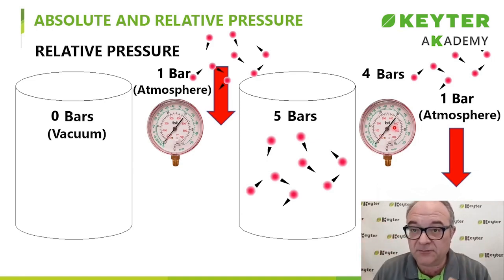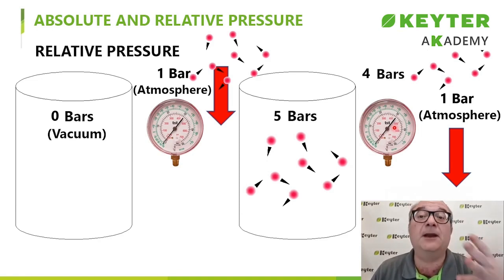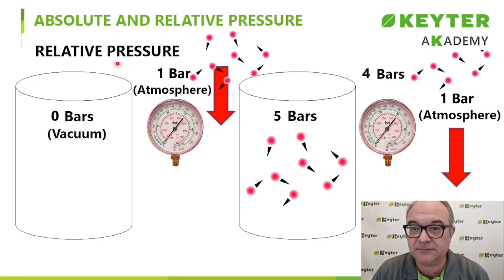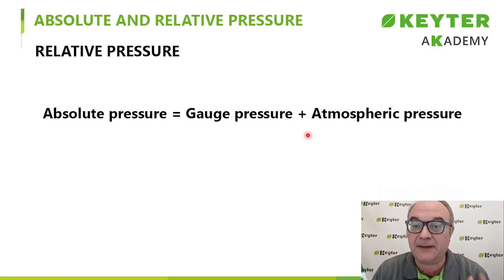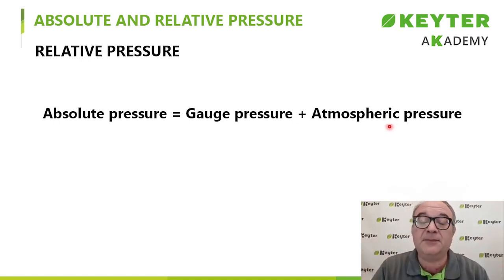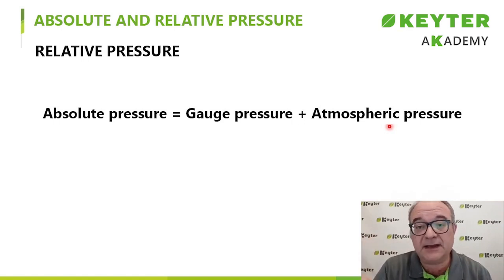This is very important because when measuring, we need to know that we are measuring relative pressures. By adding 1, which represents atmospheric pressure, we can calculate the absolute pressure, which is the actual pressure inside the tank. Thus, absolute pressure is gauge pressure plus atmospheric pressure, which is about 1 bar in this case. Be cautious with the units, as you may come across millimeters of water column, psi, kilopascals. Another topic, conversions of 1 atmosphere in psi and kilopascals, is not included in this video.